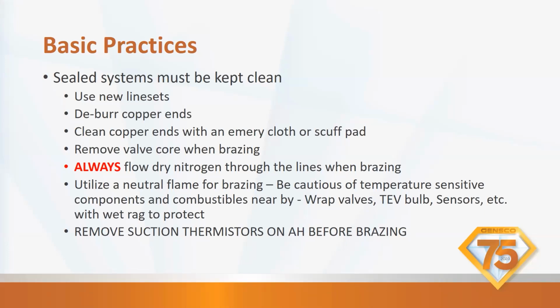Take the door off. Cut the little wire tie. Peel off that piece of insulation. Stick it on the side of the furnace. Take that sensor off, do your brazing, wait for it to cool off, put everything back, put a new wire tie on it, boom, you're done. You don't have to worry about replacing a thermistor if you do it that way. Believe me, we sell hundreds and hundreds of thermistors because they got messed up on installation.